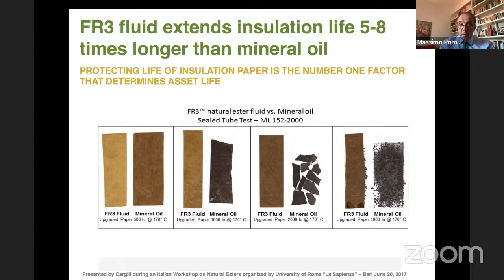This is important also because, as we will see later, this insulating liquid may work at a higher temperature. They belong to different thermal classes. I put a circle in red. You can see that according to the first line, for mineral oil and kraft paper, the thermal index is 95 degrees and the thermal class is 105.